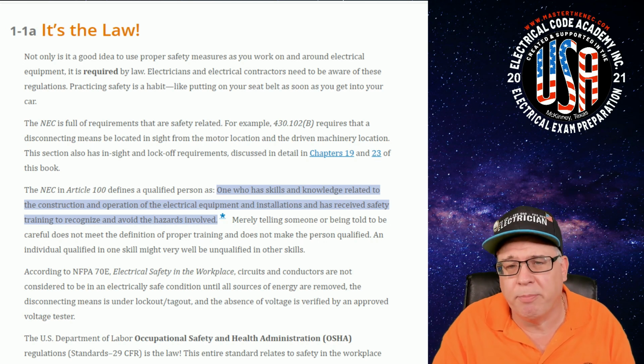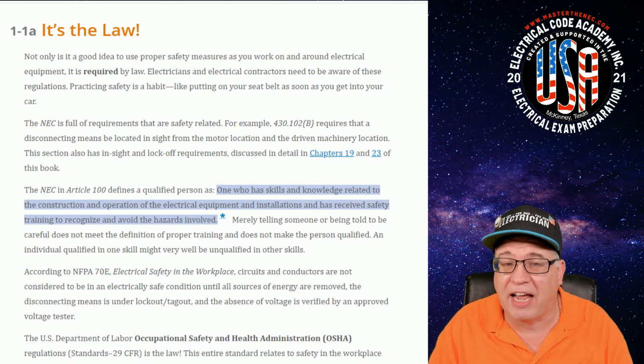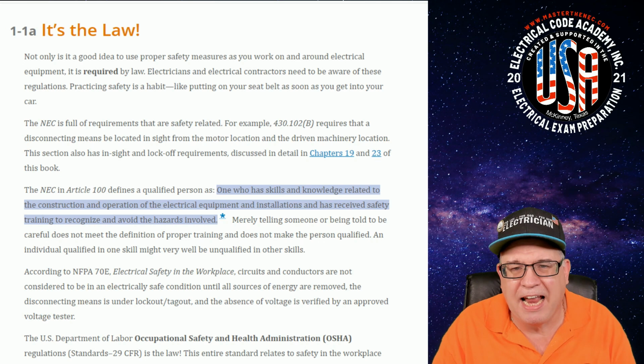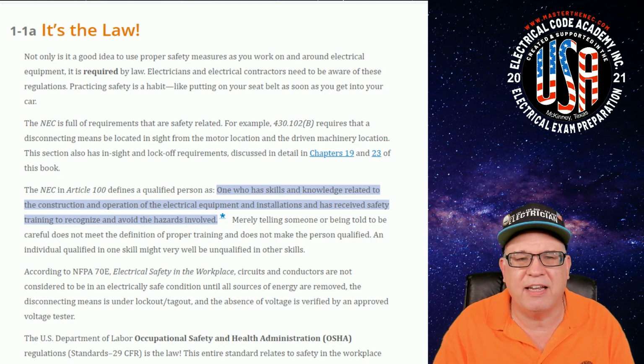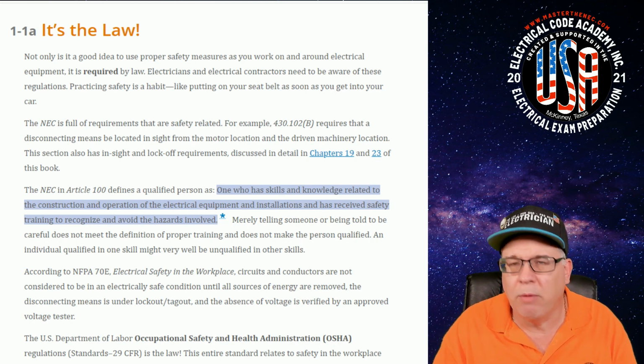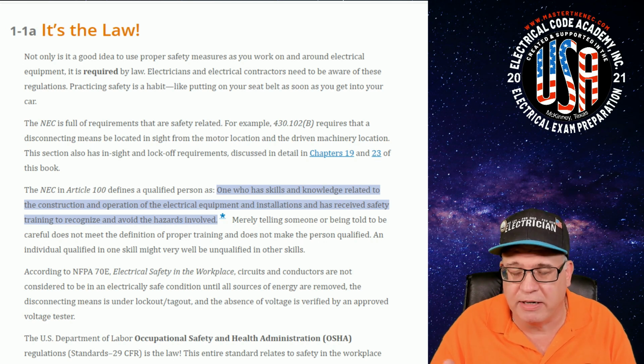For example, 430.102(B) requires that the disconnecting means be located within sight from the motor location and the driven machinery location. This section also has a within sight and a lockout requirement, which we'll discuss when we get to chapters 19 and 23 of this series.